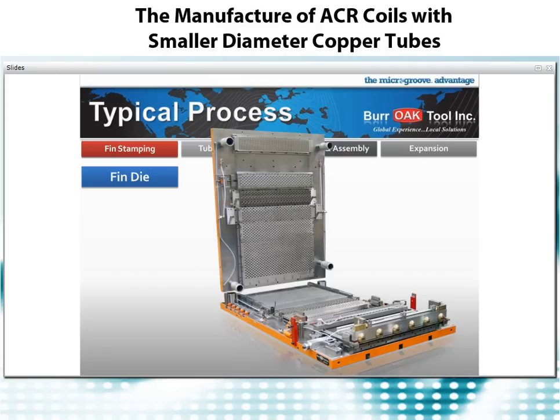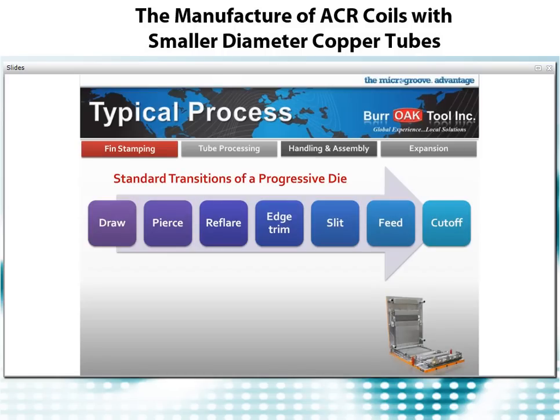The fin line supports the fin die — the actual tooling that determines the configuration of the fin itself. It is a progressive type die and can be either a draw or an extrude design. A progressive die moves the material in specific increments, performing a unique task at each station. In the fin die, the usual stations are: the draw, which governs material for the collar; the pierce, making the collar hole; the flare, determining the final collar height; the edge trim, finishing the outside edges; the slit, determining the number of rows wide in each fin; the feed, providing movement of the fin stock through the die; and the cutoff, which makes the correct length of fin.